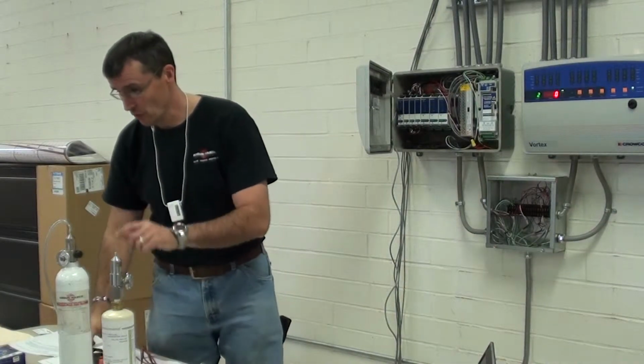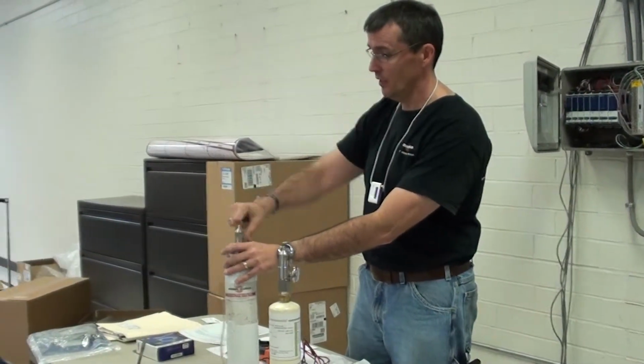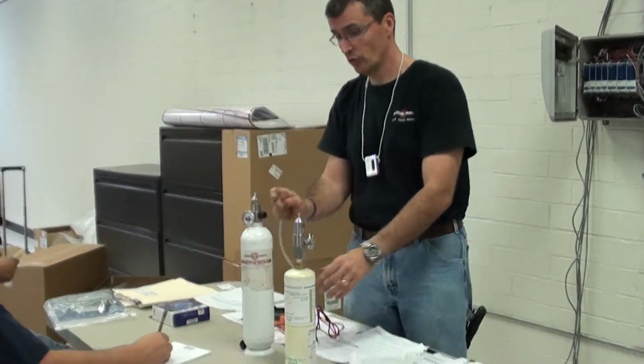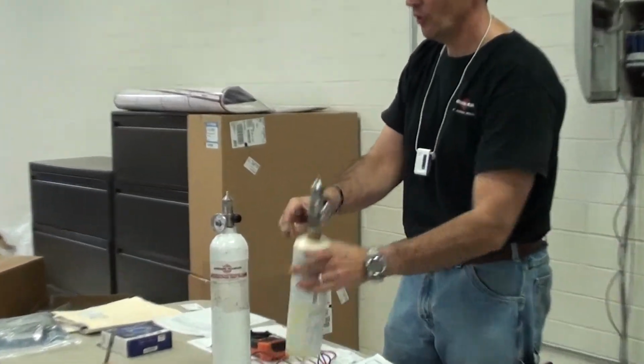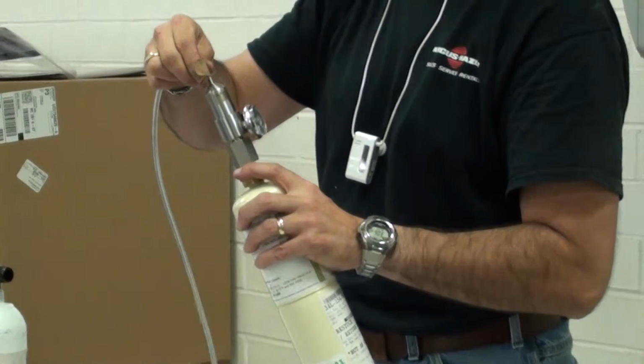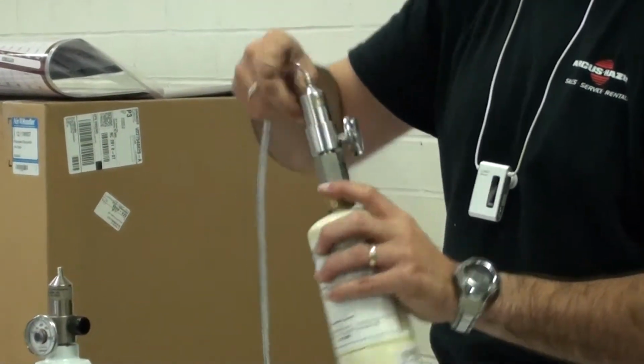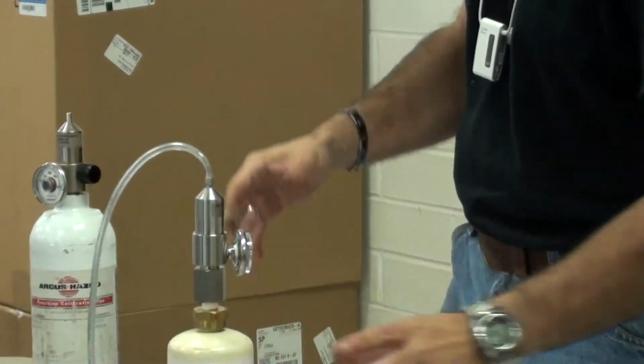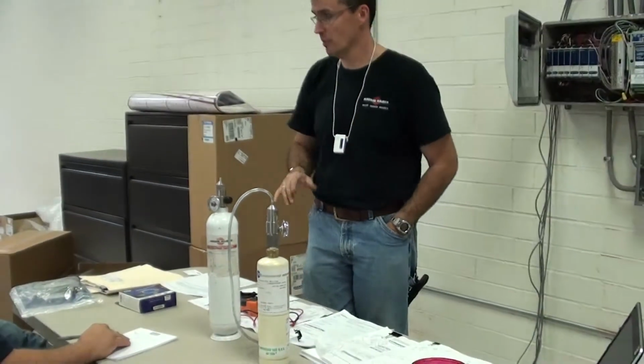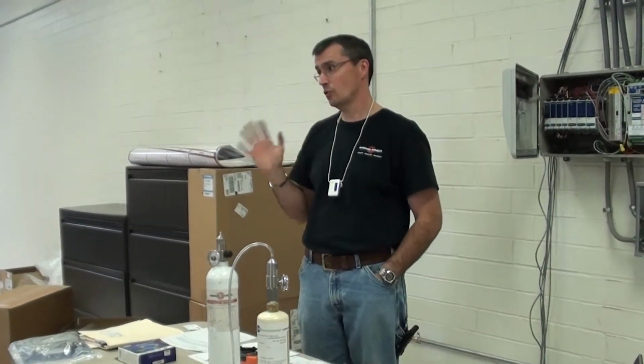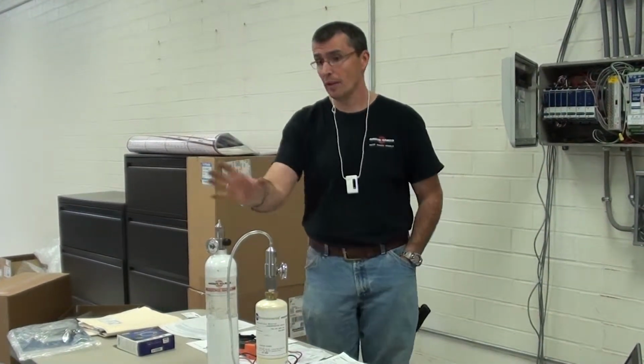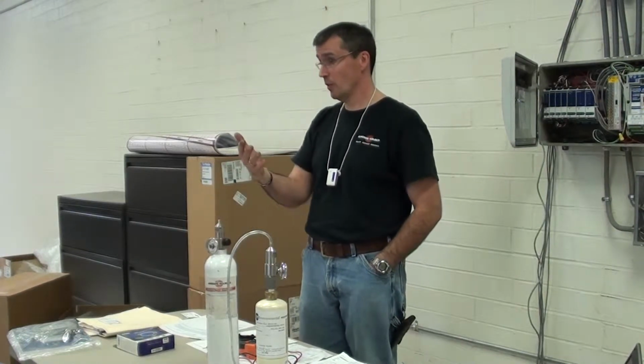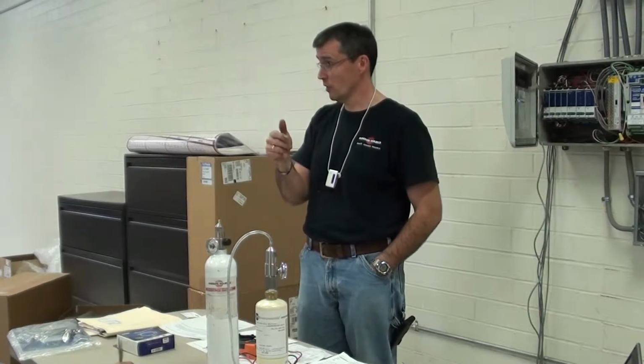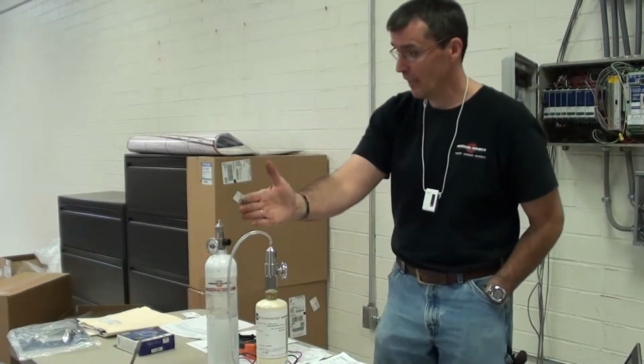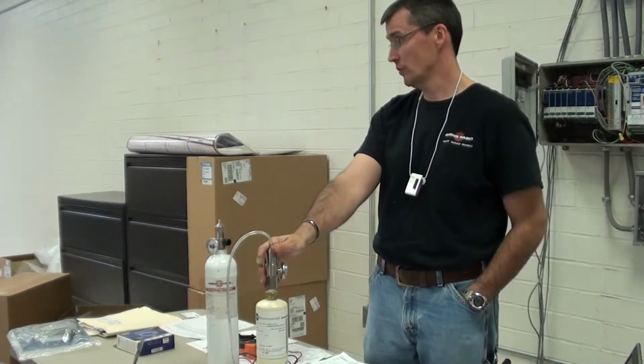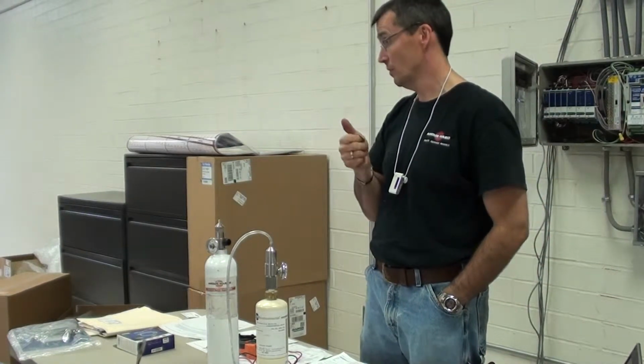So once we've got our zero set, if you only have one regulator, you'll unscrew your regulator and place it on your pentane. And then you're going to apply your pentane. It's recommended that you leave this gas applied anywhere from 1.5 minutes to 2 minutes. So when you apply the zero gas, let it purge for 1.5 to 2 minutes before you set your zero. When you go to your span gas, you're going to let it flow for 1.5 to 2 minutes before you adjust your cal pot.